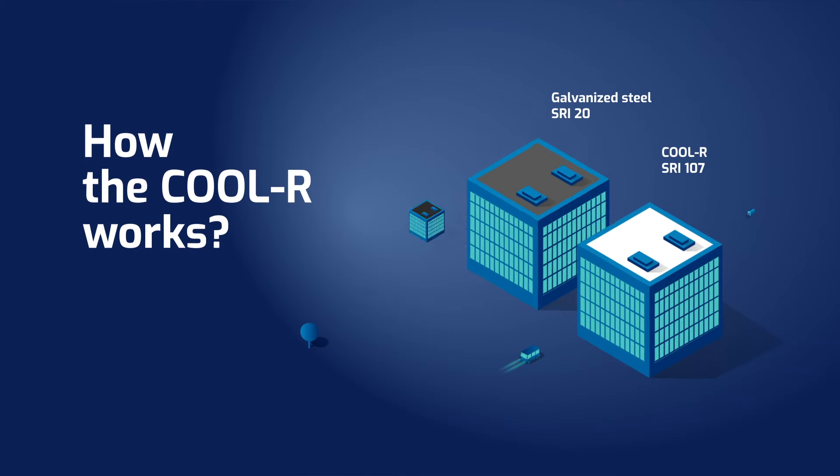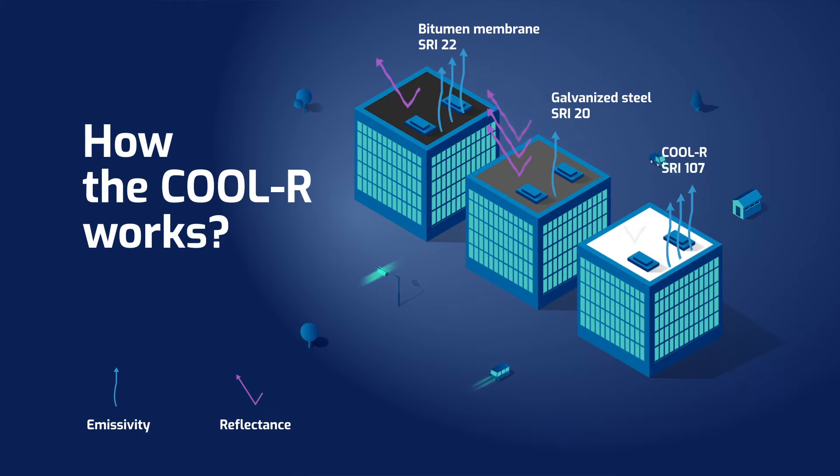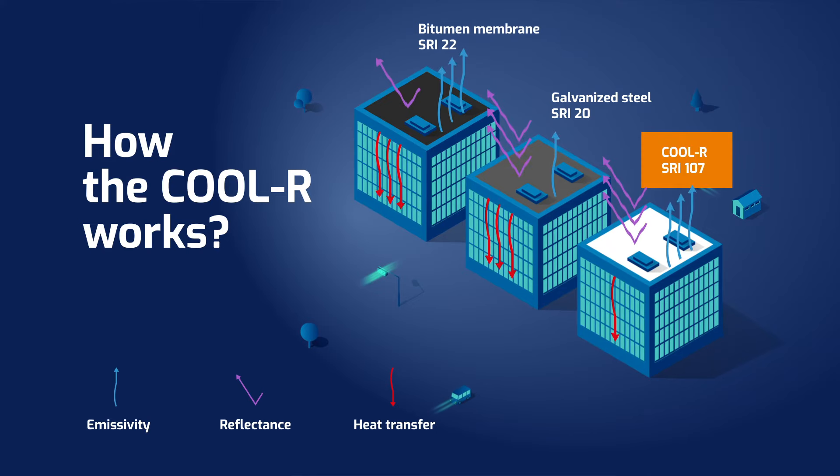COOL-R coatings have both high emissive power and reflectance. The first is responsible for the ability to dissipate absorbed heat. Its reflective abilities, on the other hand, allow you to reflect thermal radiation. Together, they shape the SRI, Solar Reflectance Index parameter, which expresses how well a given material reduces the effects of solar radiation. The higher it is, the less heat enters the building.